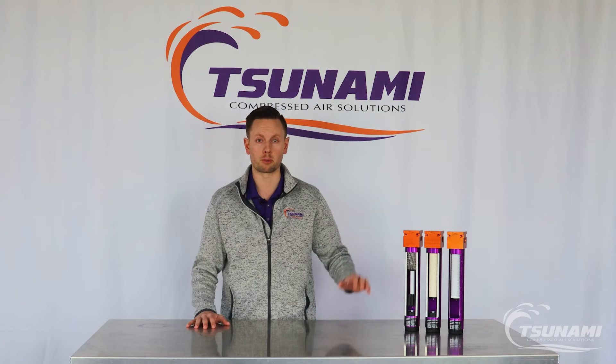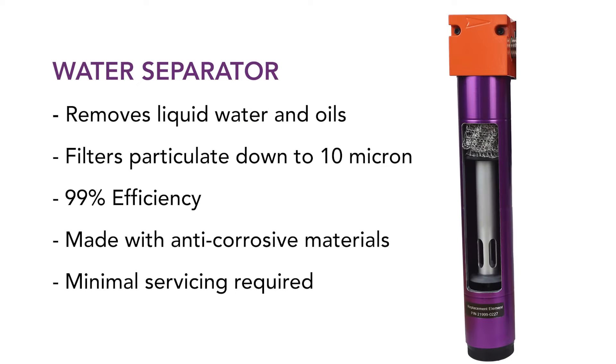The first one is our water separator. The water separator is designed to remove bulk liquids like water and oil, as well as removing particulate down to 10 micron.